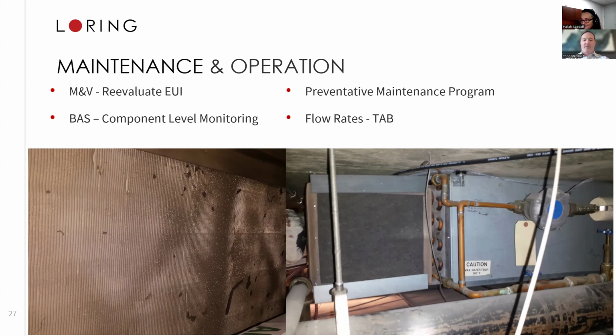change schedule. Filter changes also matter, especially since Hala was bringing up VRF and refrigerant systems. If the filters on those systems start getting clogged up on the evaporator coil, you can lead to other maintenance problems like icing up of the DX coils. As your filter loads up with more and more dust, it actually restricts airflow more and more and becomes a more efficient filter.